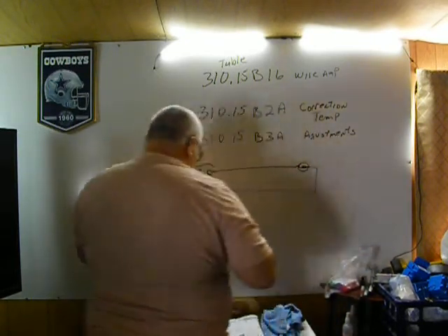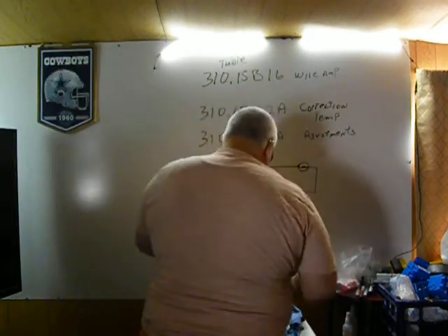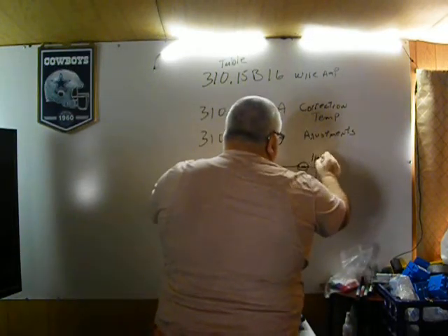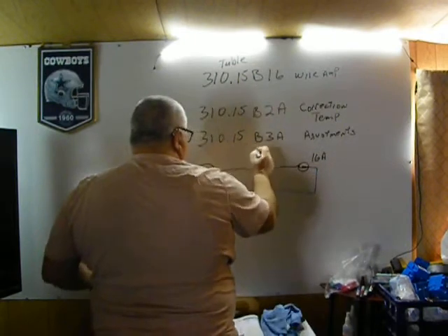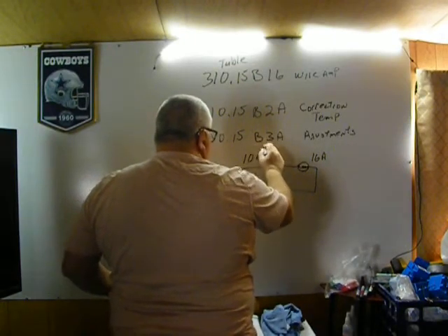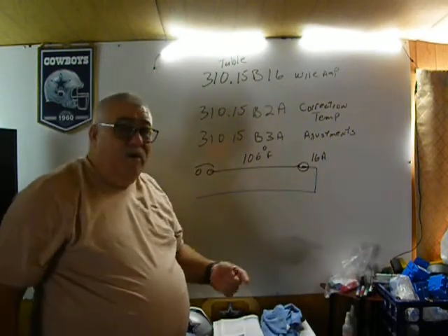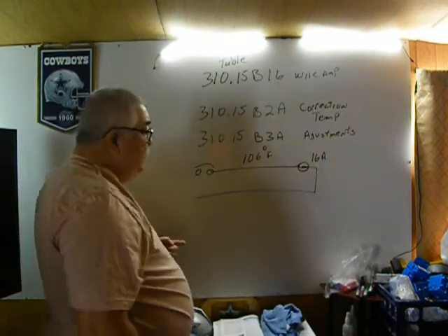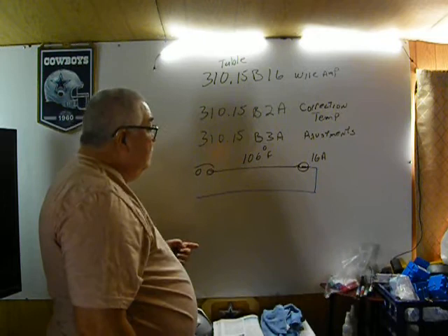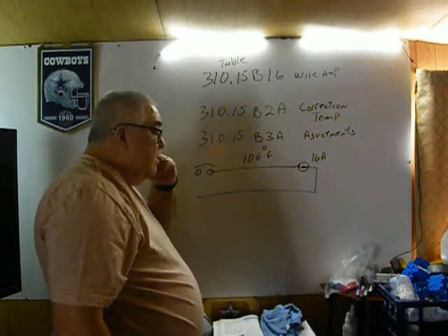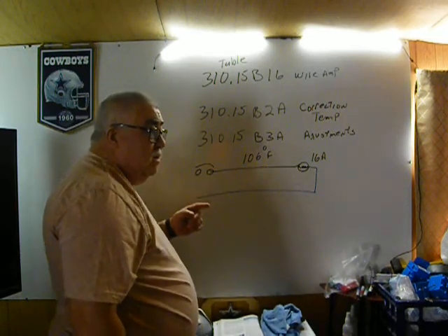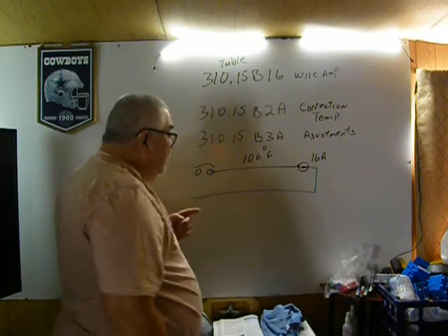I'll come back with the neutral. I got 16 amps and my temperature is 106 degrees Fahrenheit. Okay, what size wire do I need? Well, off the top of my head, I can use a 12 gauge wire.